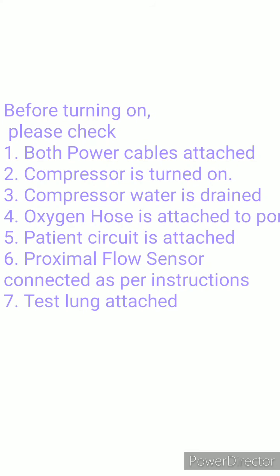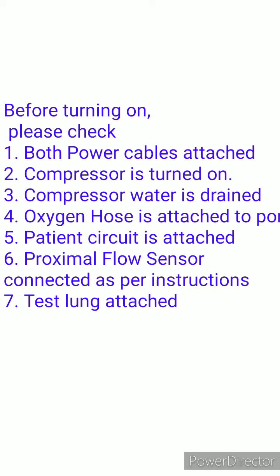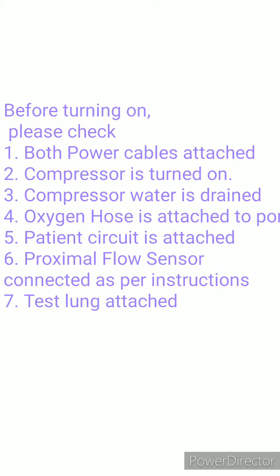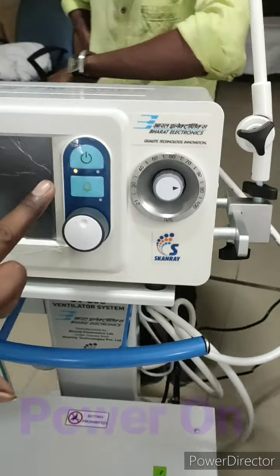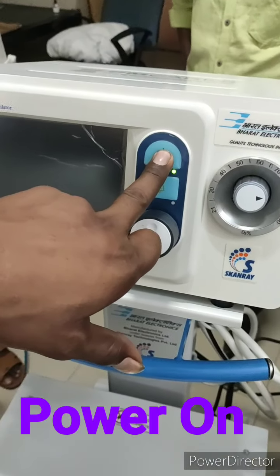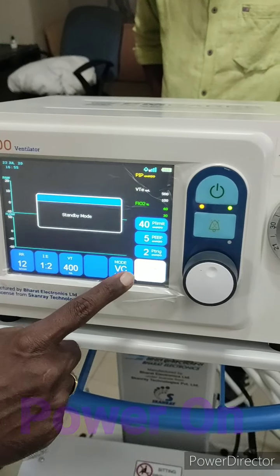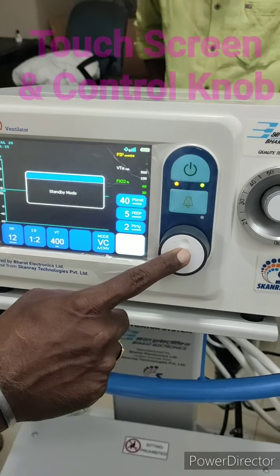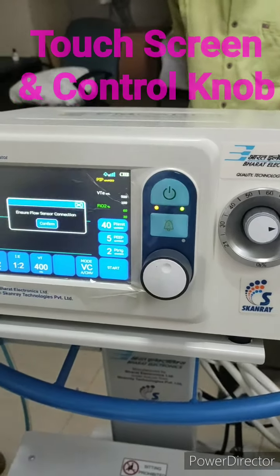Before turning on the ventilator, please check that both power cables are attached, compressor is turned on, compressor water is drained, oxygen hose pipe is attached to the port, patient circuit is attached as per the instructions with proximal flow sensor and test lung. How do you turn on the machine? This is power on. Okay, touch screen. So you touch on the start button and then press the knob.